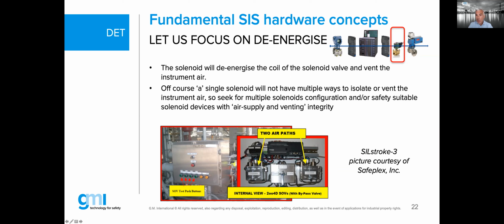And why is that? Because those instruments tend to be in one position for many months, which is typically always the opposite position of safety. Because you try to keep your plant running, you try to keep your production ongoing. That means those solenoids, those final elements, are typically in an open position, enabled to produce. Enabled to go to safe position, you have to move those items. And if they haven't been moving for a long time, problems like being stuck on mechanical issues in such types of systems are typically known in our industry.